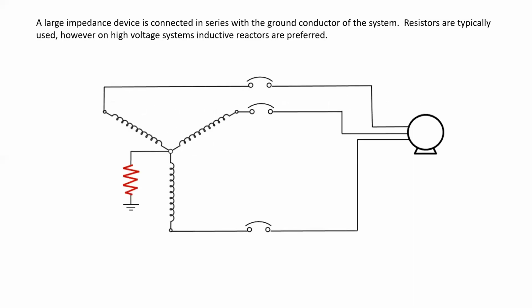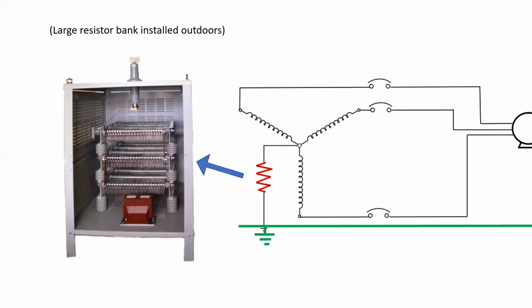In a high impedance system, a large impedance device is connected in series with the ground conductor of the system. Resistors are typically used. However, on high voltage systems, inductive reactors are sometimes preferred. And so we can see that resistor outlined in red. It often looks like a humongous three-phase toaster or heating element. It's usually situated outdoors because when current flows through it, it's going to generate a significant amount of heat.